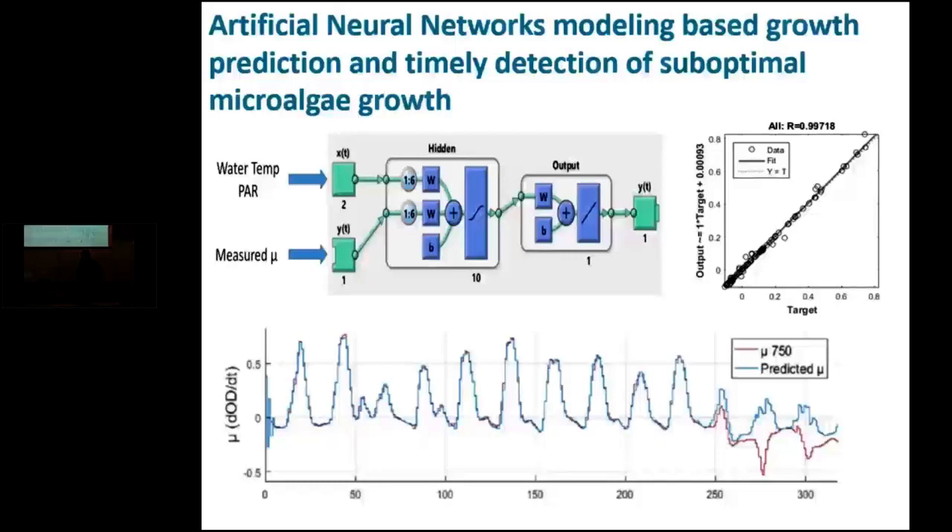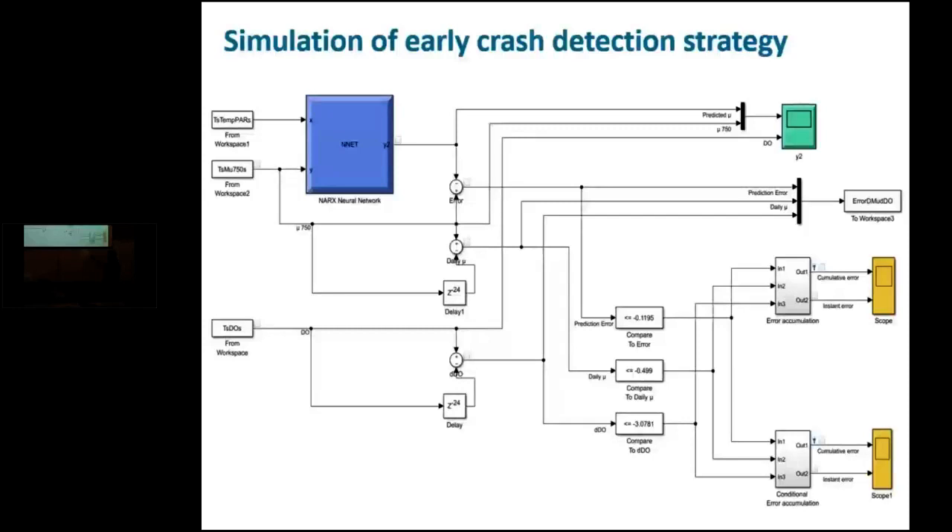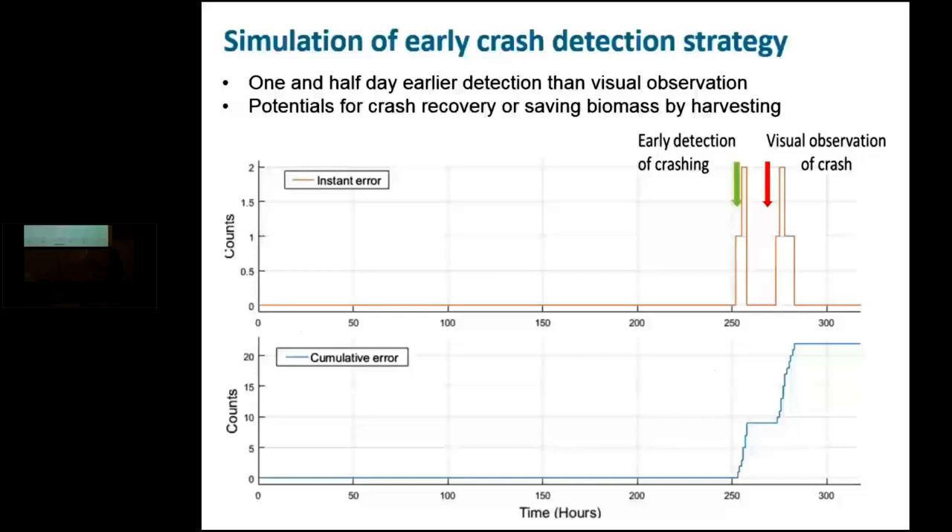You're looking at that approach and strategy here. I'm showing just one variable because of space limitations, but the approach actually looks at three other key features to track trends and detect anomalies. Here we see the crashing, and the model prediction is really nice and accurate using neural network-based predictive modeling and statistical decision-making to count flags based on measurements and provide that information to the operator.